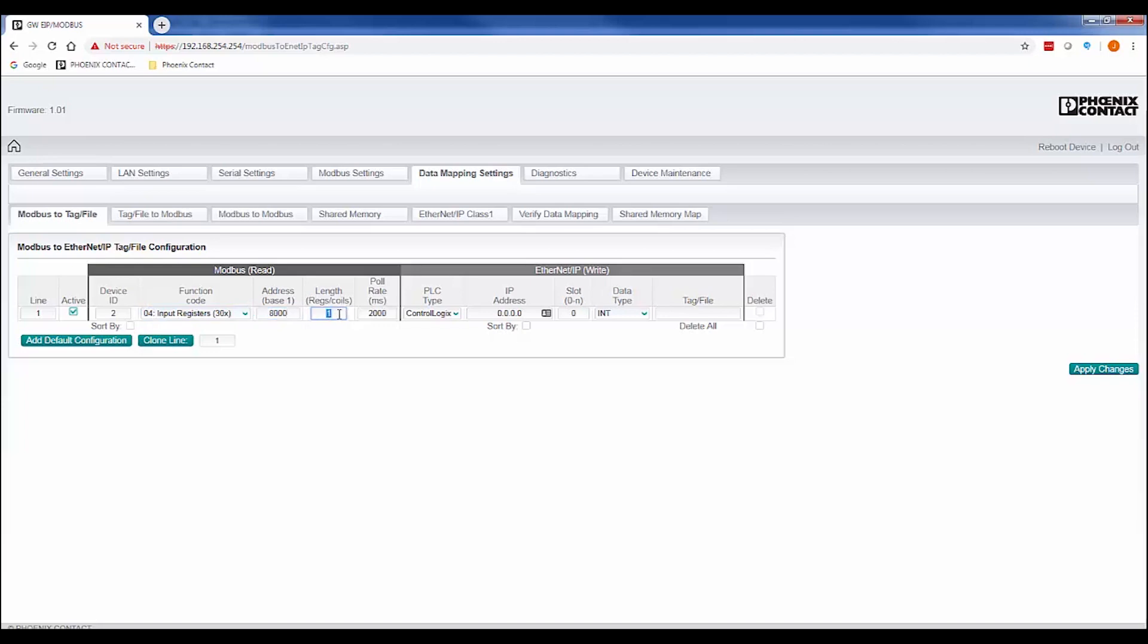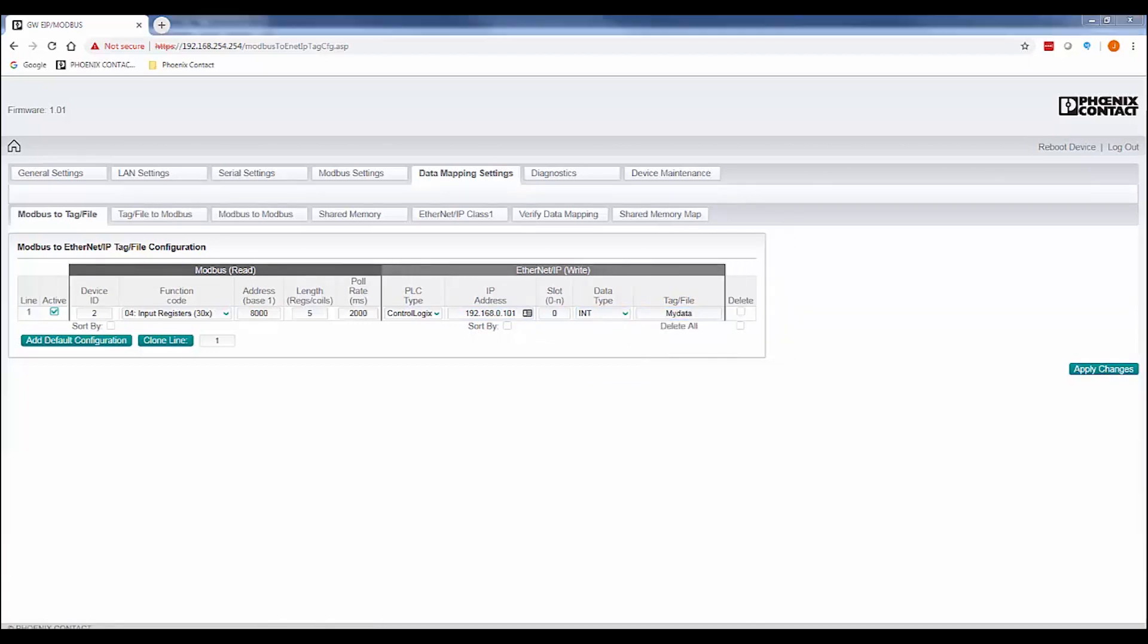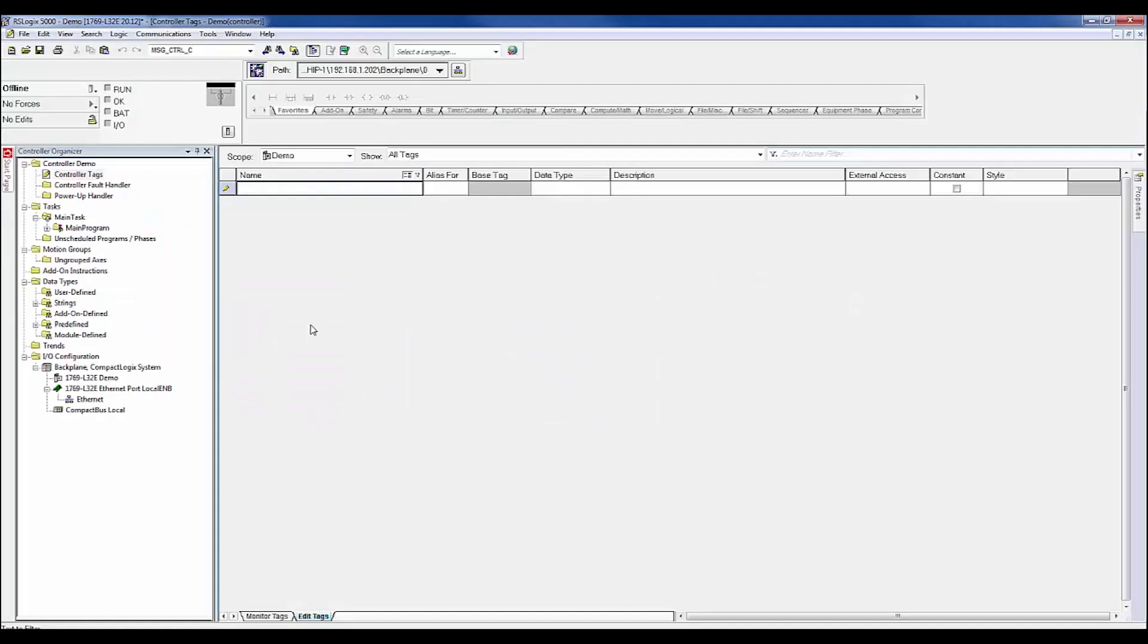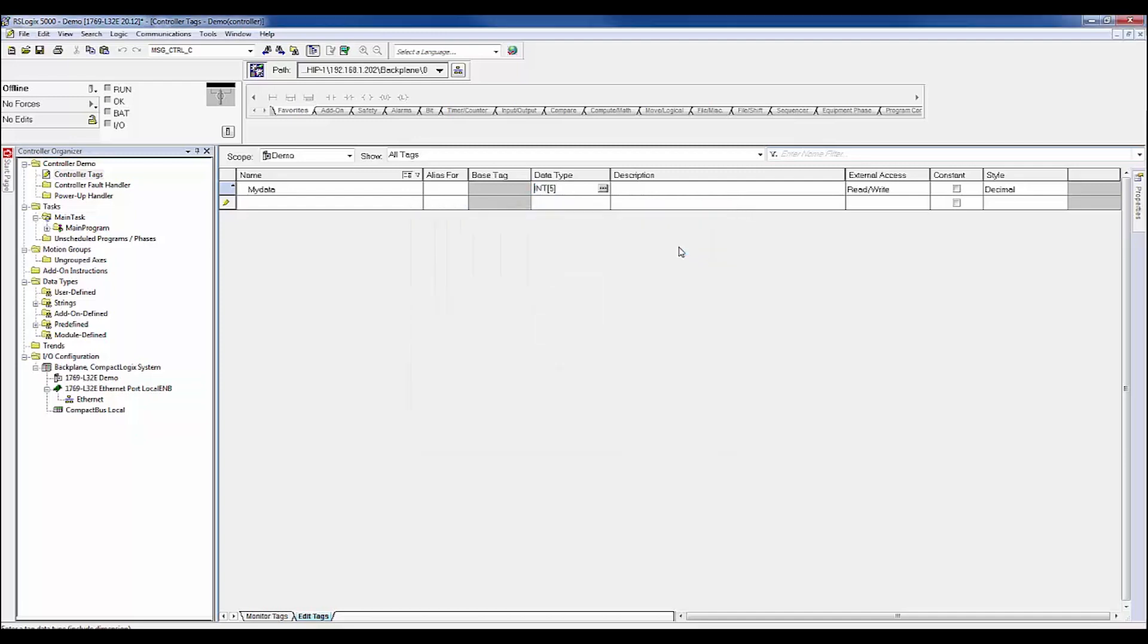Then select where this information is going to be passed. In this example, we're writing this information to a ControlLogix PLC at the following IP address and to the following controller tag. Then we can switch to our RSLogix project and add a tag with its exact name, data type, and dimension if the tag is part of an array. If that was the only data we needed, we could compile and download the project to the PLC and data would start transferring.